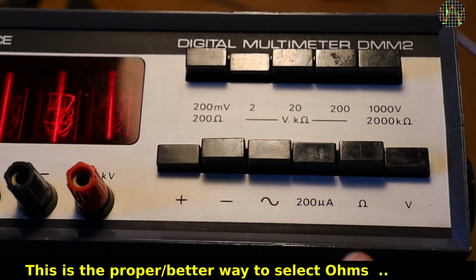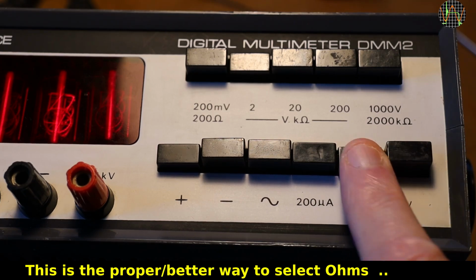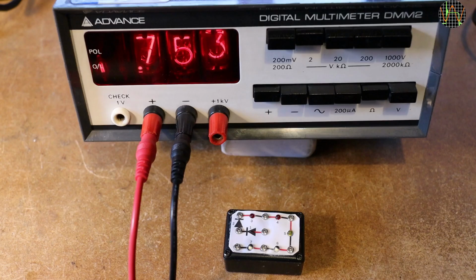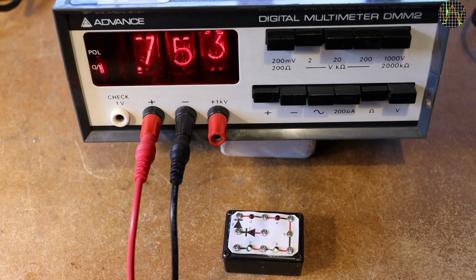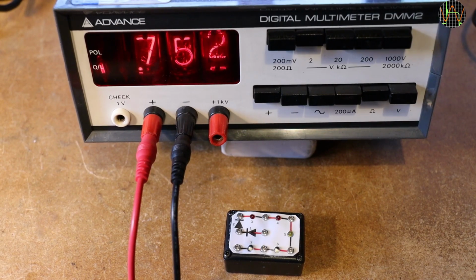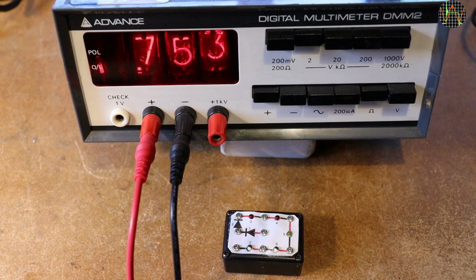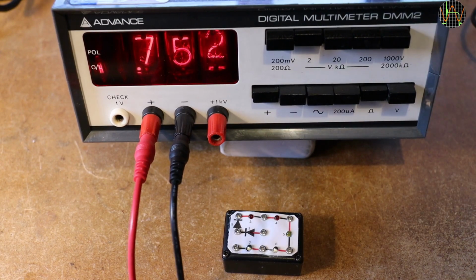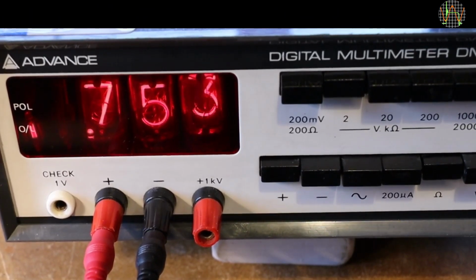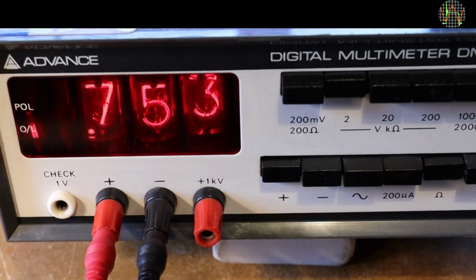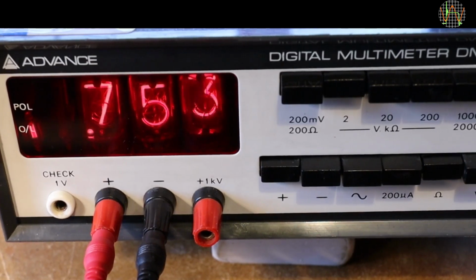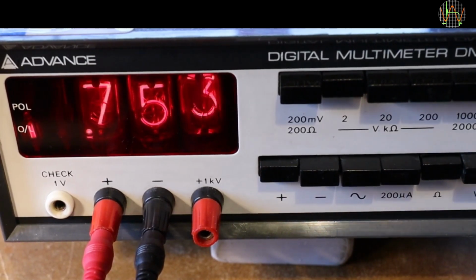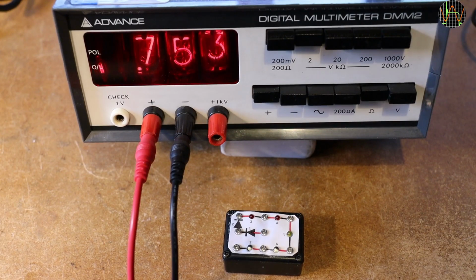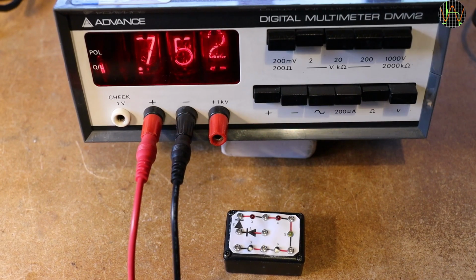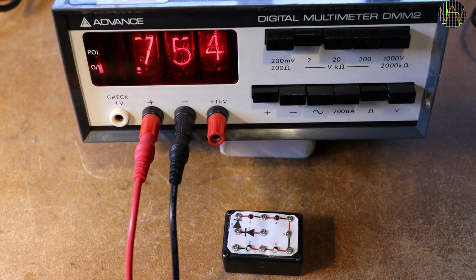You also realize that flawlessly operating this deceptively easy looking multimeter may require some training. Although the manual doesn't say anything, in line with other vintage meters, you can use the 2K ohms range for diode test. But hold on to your hat, the ohms voltage is 11 volts with 1 milliamp current. Also, for open circuit, that is diodes in reverse direction, you have to get used to ignore the number in the display because the OL light is on.